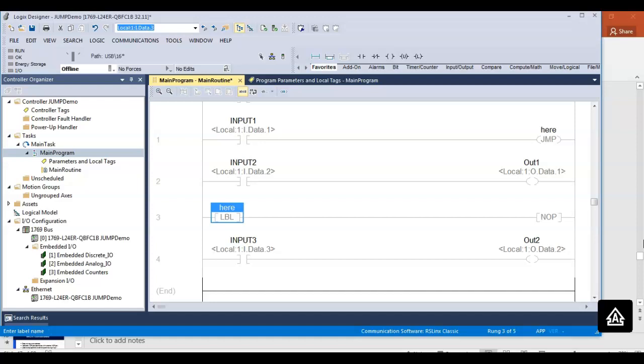It's just that a no op instruction basically does what? Nothing. And you don't sacrifice a memory bit for anything. It doesn't go true, it doesn't go false. It gives you the ability to put an instruction at a rung that basically does nothing. And that's what it says. It's a no op, right? No operation. So we can download this and it would work exactly the same. But here we're not using a bit instruction or internal. We're not using one of our internal bits.